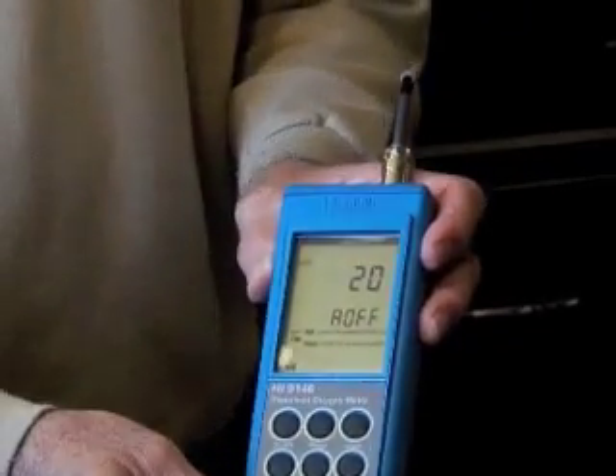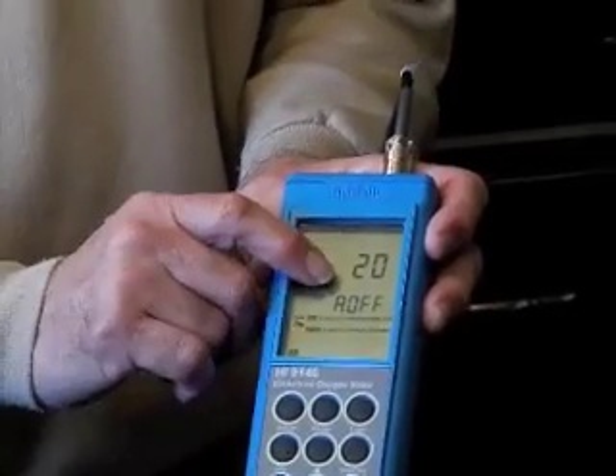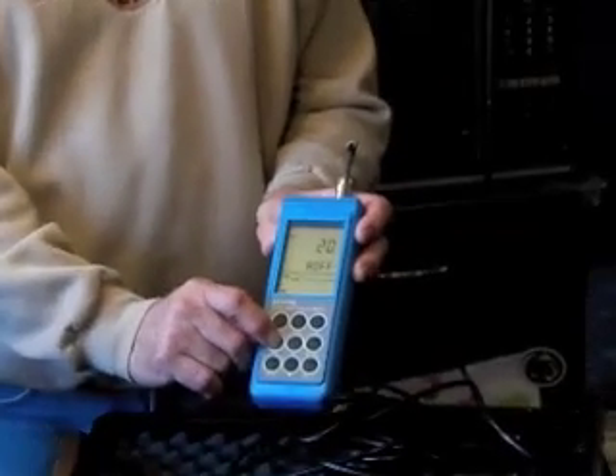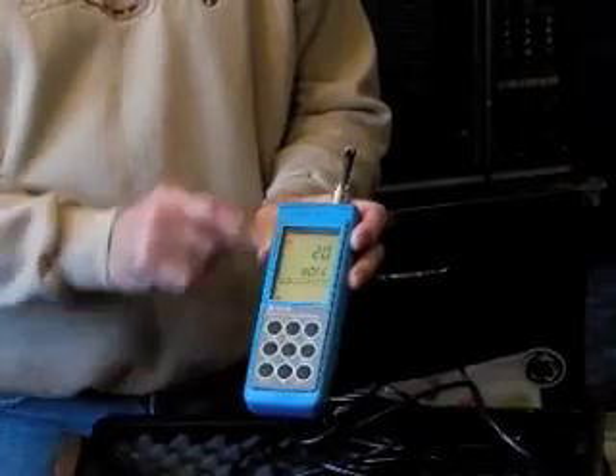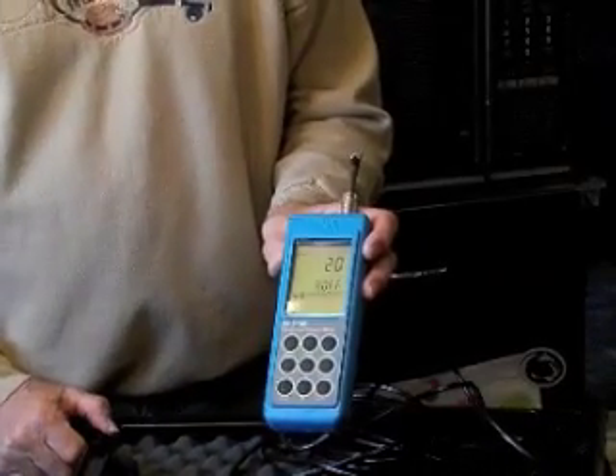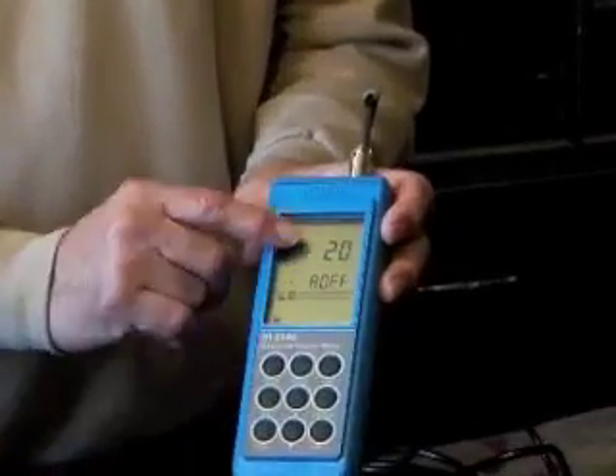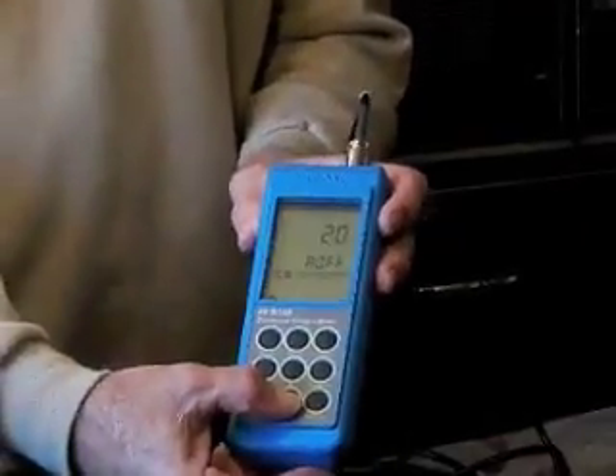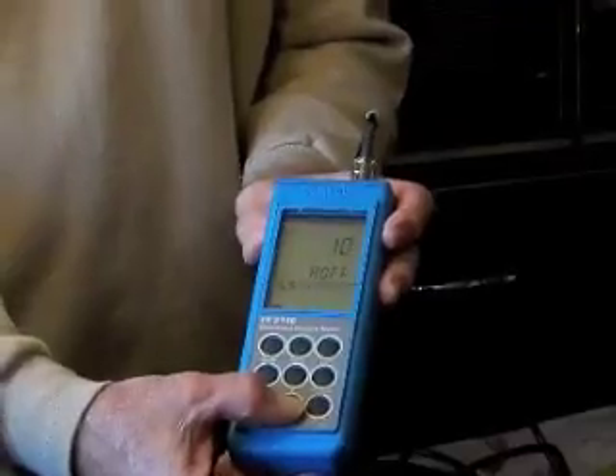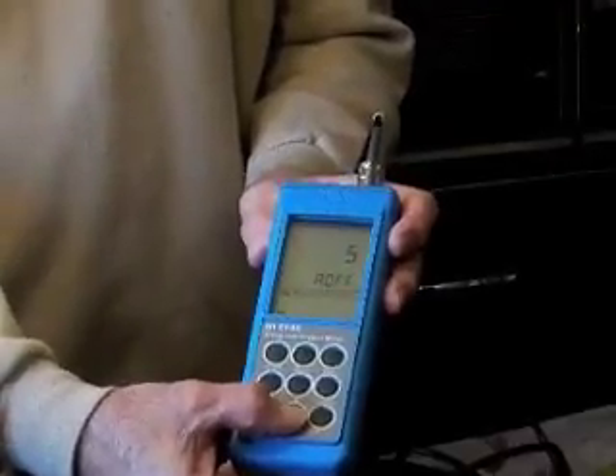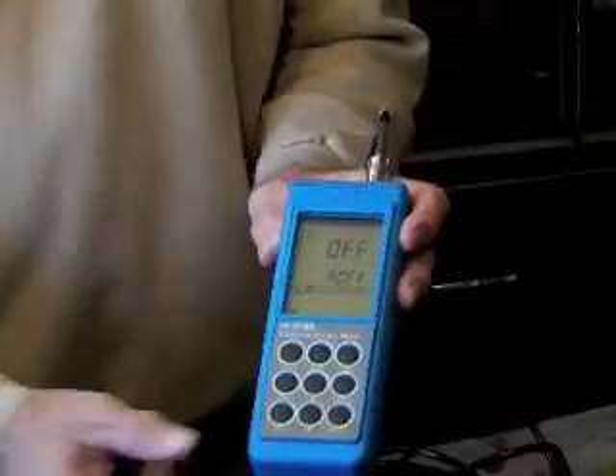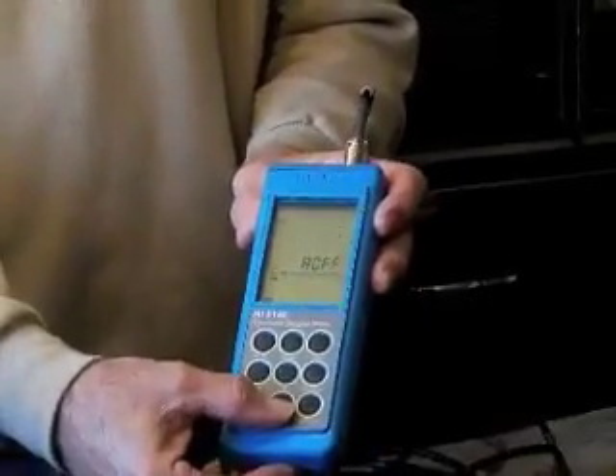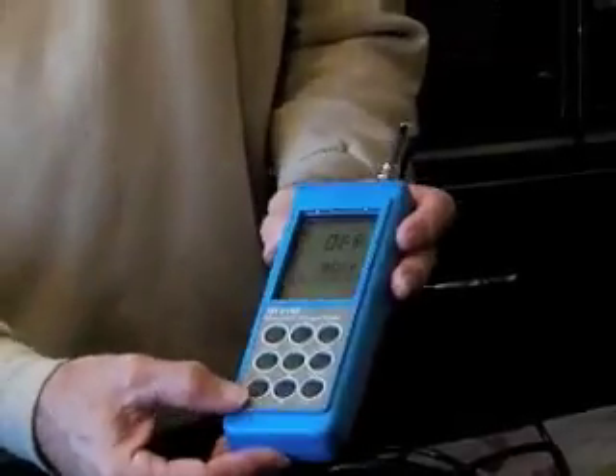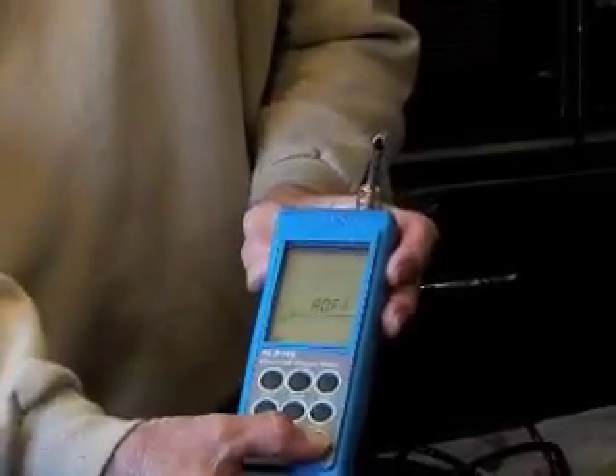So at this point, remember, when you want to change that number, you hit the calibration button, and then the 20 will flash, and that's telling you it's ready to change. And then you can use your up and down arrows. I think it changes in 5-minute increments, so 10 there, and then it goes down to 5, and then your next choice is off. All right, so I just hit the down arrow button a few times and got it down to off, and then you just confirm that you want to turn it off.